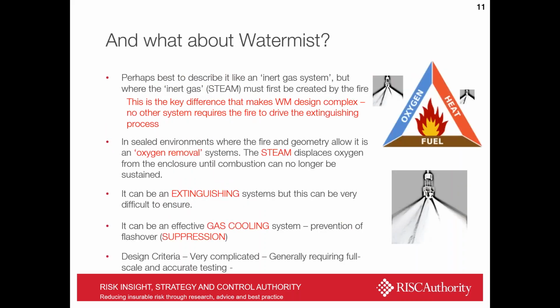So what about Watermist? Well, perhaps it's best described as though it's an inert gas system, but in this case, the inert gas is steam, and that must be created by the fire itself. And actually, it's this complexity that makes this different from any other extinguishing system, because how it works, how well it works, and the way in which it works is driven by the fire itself. And not just by the fire itself, but the relationship that the fire has with the enclosure that it's within. And really scale becomes a very important factor here. A big fire in a small compartment might behave very differently to a small fire in a very big compartment. And even during the life cycle of the fire, these properties can change as the fire grows and shrinks.